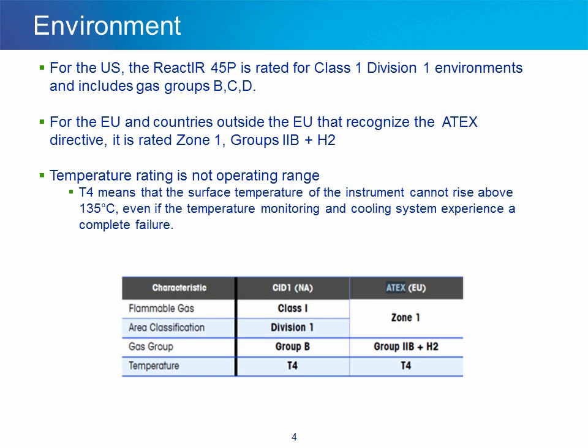In the U.S., the ReactIR 45P is rated for Class 1, Division 1 environments, and that includes gas groups B, C, and D. For the European Union and countries outside the EU that recognize the ATEX directive, it is rated Zone 1, gas groups IIB plus hydrogen. The temperature rating is T4, meaning the surface temperature of the instrument cannot rise above 135 degrees Celsius under any circumstance, even if the temperature monitoring and cooling system experience a complete failure.